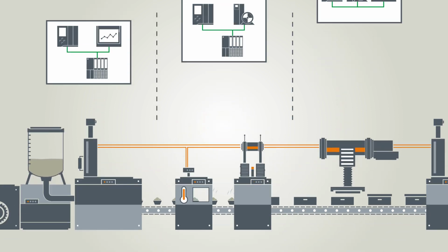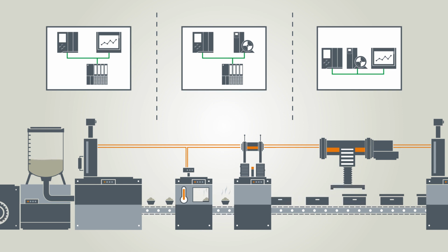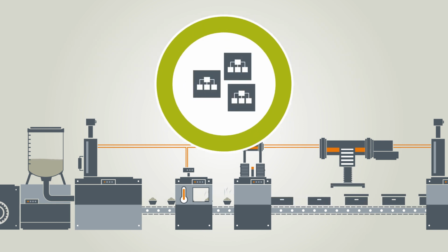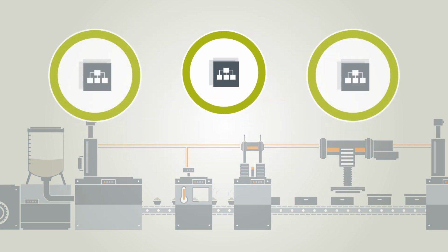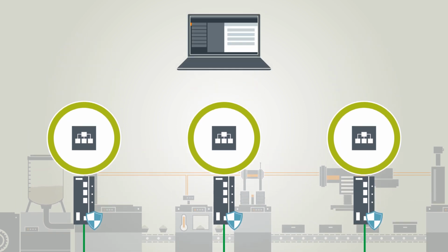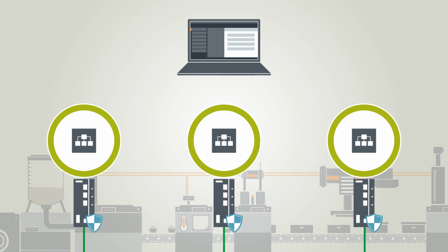The network segmentation, which means the segmentation of the plant network into individually protected automation cells, serves to reduce risk and increase security. In practice, components with security integrated assume these protection tasks, which are of course configured in the TIA portal. Let's take a look at an example of this.